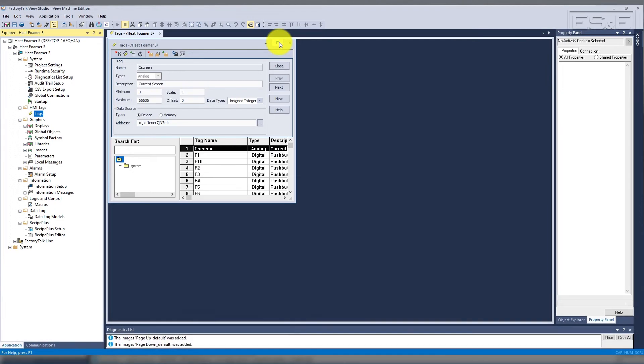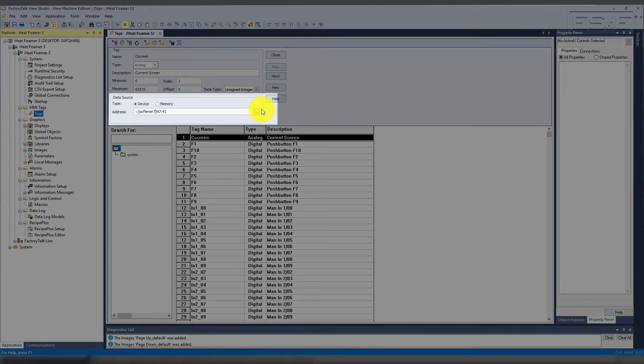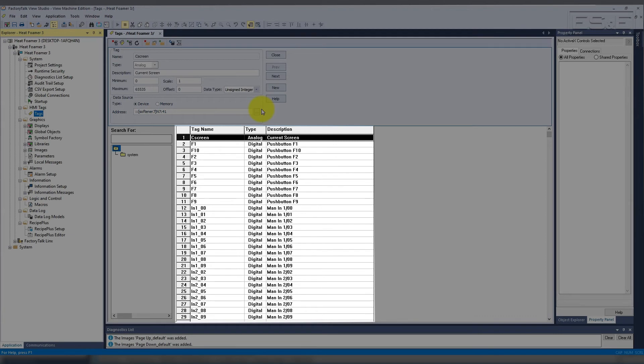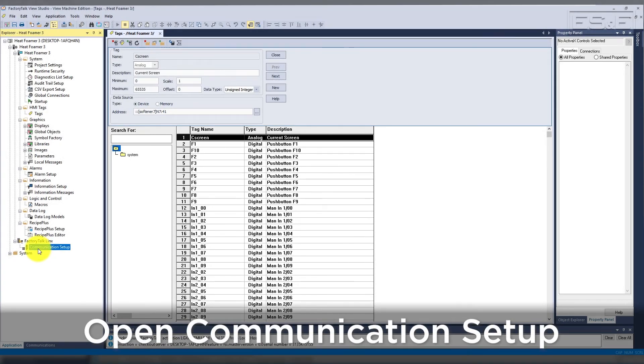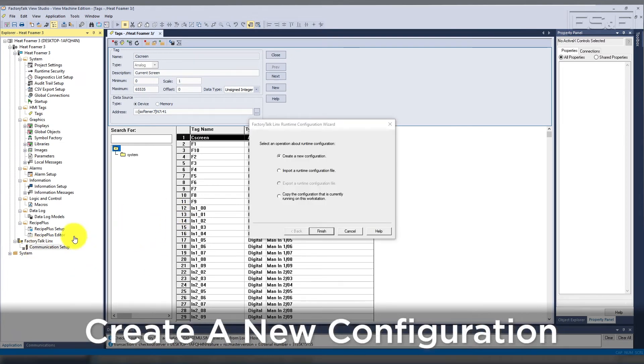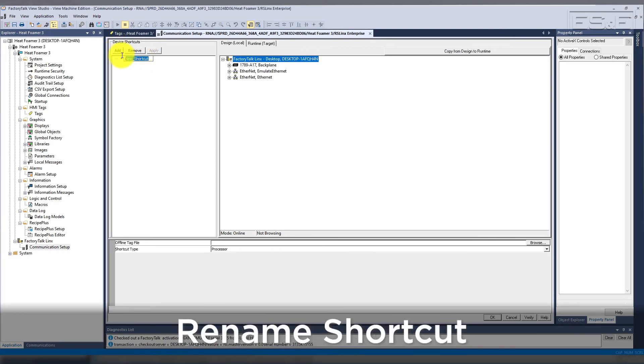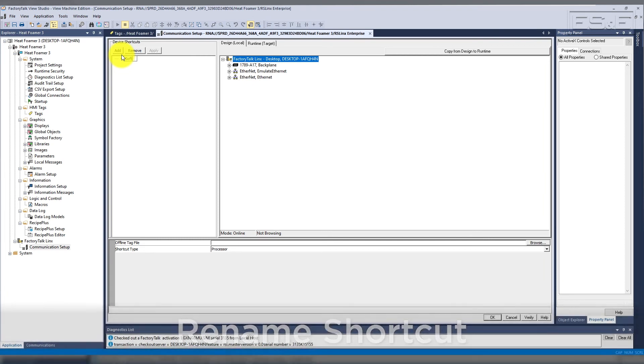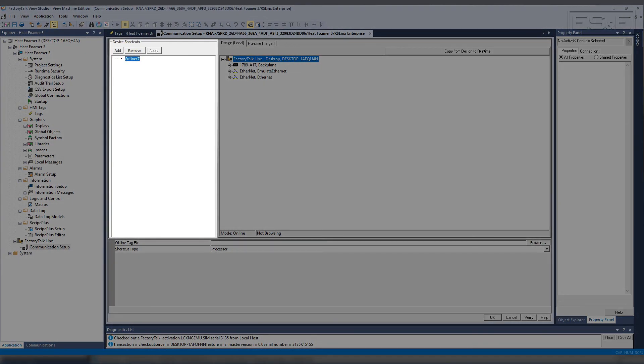The last item I'd like to talk about is the communication setup for your conversion. I'm not going to address protocol-specific items, but the conversion creates what are called HMI tags. Open the tag folders under HMI tags — notice the node name in the Panel Builder 32 file will be used as the prefix or shortcut name for every HMI tag in the application. When you go in to do the communication setup, select 'Create a New Configuration' and then Finish. Select Add, then change 'New Shortcut' to the shortcut name used as the prefix in the HMI tags. Once that shortcut name is associated with the physical controller, the values of the tags in the controller will populate the HMI tags in your converted application.